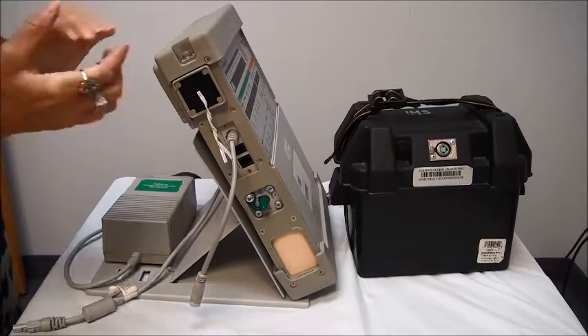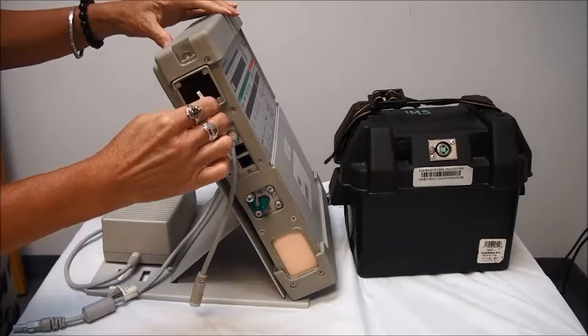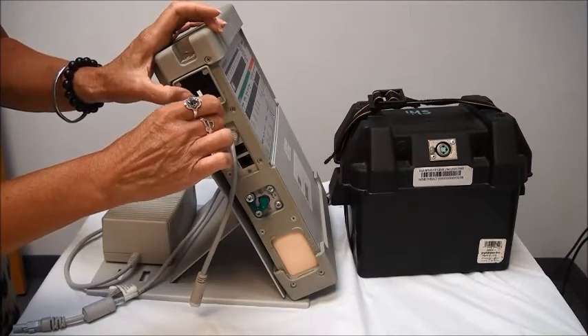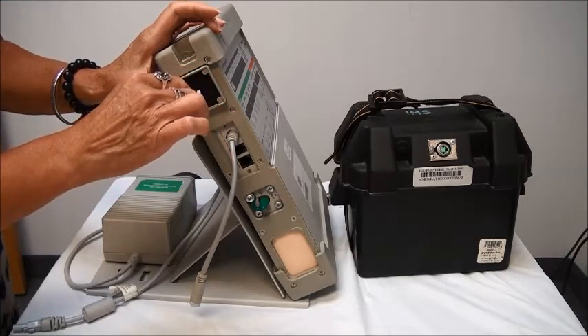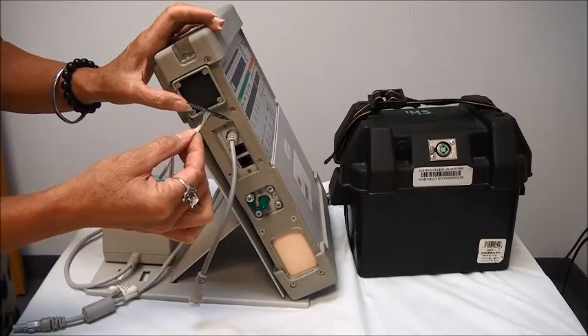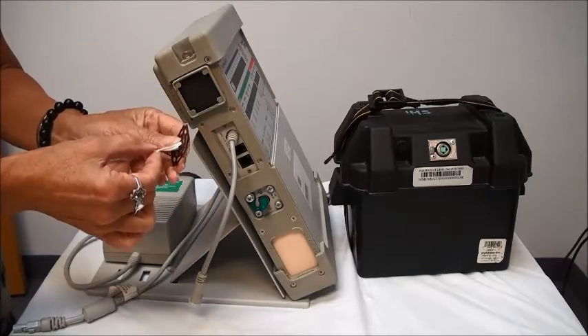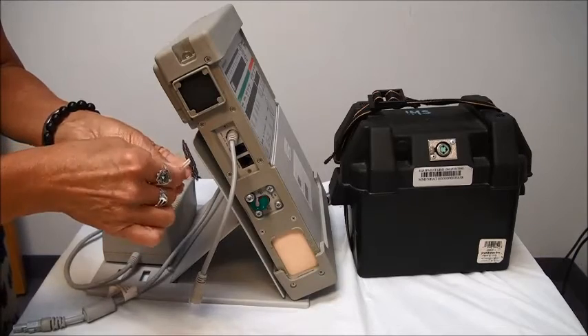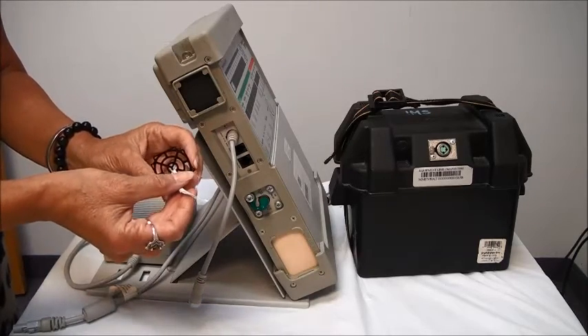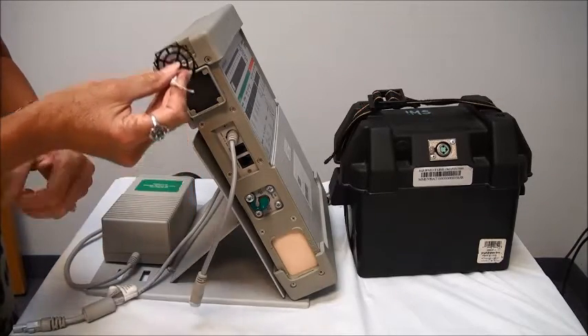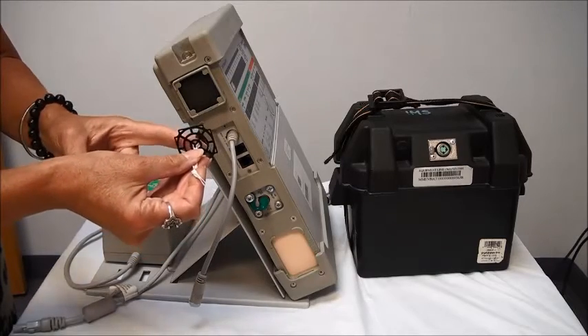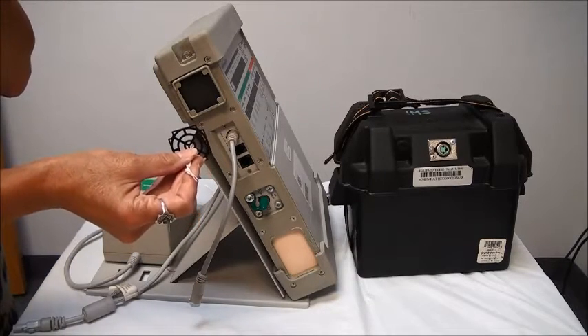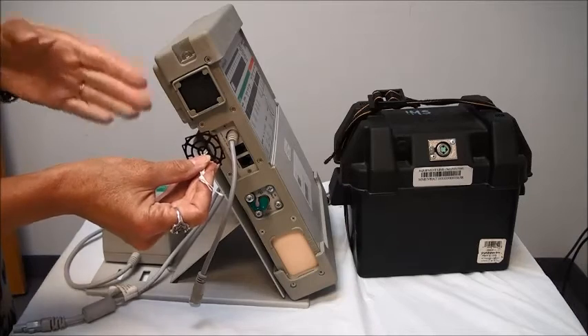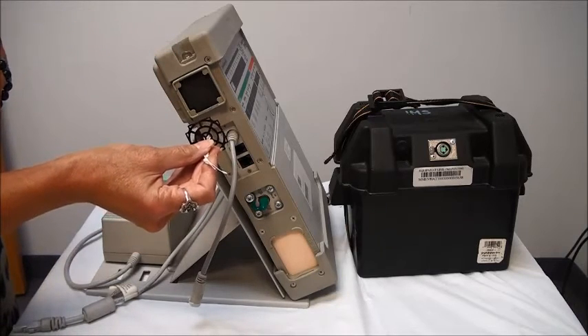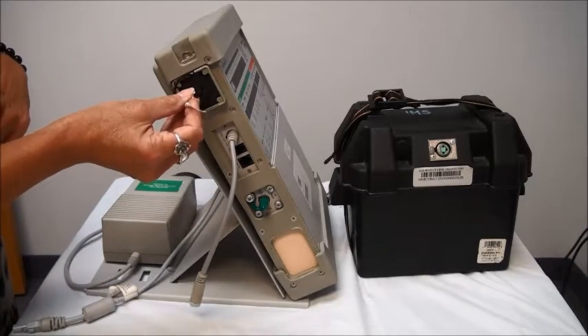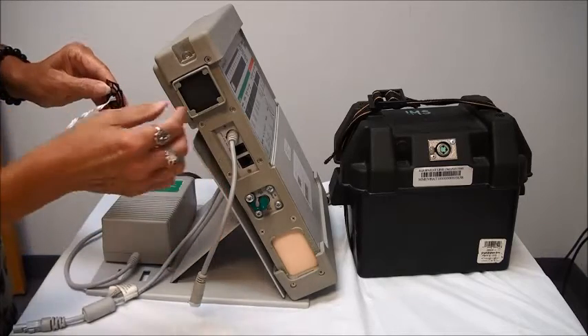So you can either take your fingers, or what sometimes people will do is attach a twist tie to the filter cover so it makes it easier to pull it out. If you do decide to go with this method of using a twist tie, make sure you remove the filter cover before installing the twist tie so that you're not having the same issue of poking into the ventilator. So what you'll want to do is pull the filter cover off.